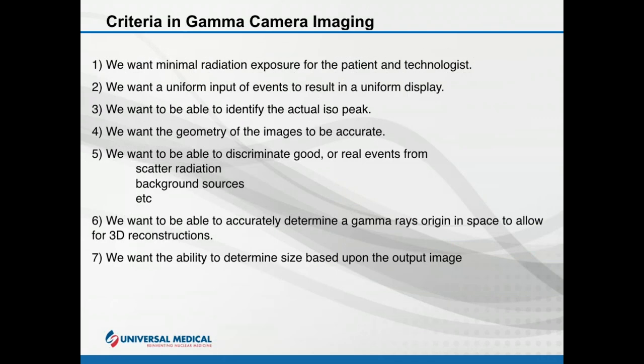When we talk about a gamma camera, we have some criteria we want to accomplish. We want radiation exposure for the technologist and patient to be as minimal as possible. We want the detection device to provide a uniform display for a uniform input — input must equal output. We also want to be able to identify the ISO peak, or energy of the isotope being utilized. Without that ability we can't distinguish between good events and garbage events.